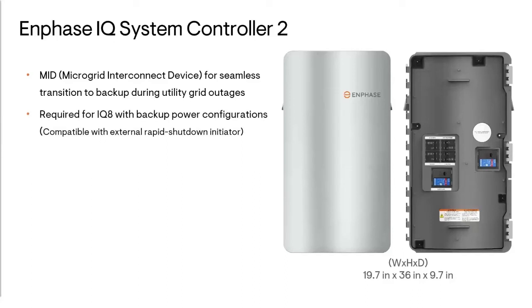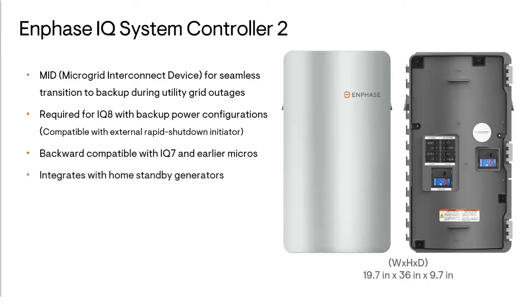The IQ System Controller 2, specifically the 2, must be used whenever installing IQ8s on the solar array. The original IQ controller can't be used with IQ8s because it doesn't have the required hardware for rapid shutdown requirements. That said, the IQ System Controller 2 is backward compatible with IQ7 and earlier microinverters. Both the original and the new IQ System Controller 2 can integrate with home standby generators, which can operate in parallel with solar and battery.